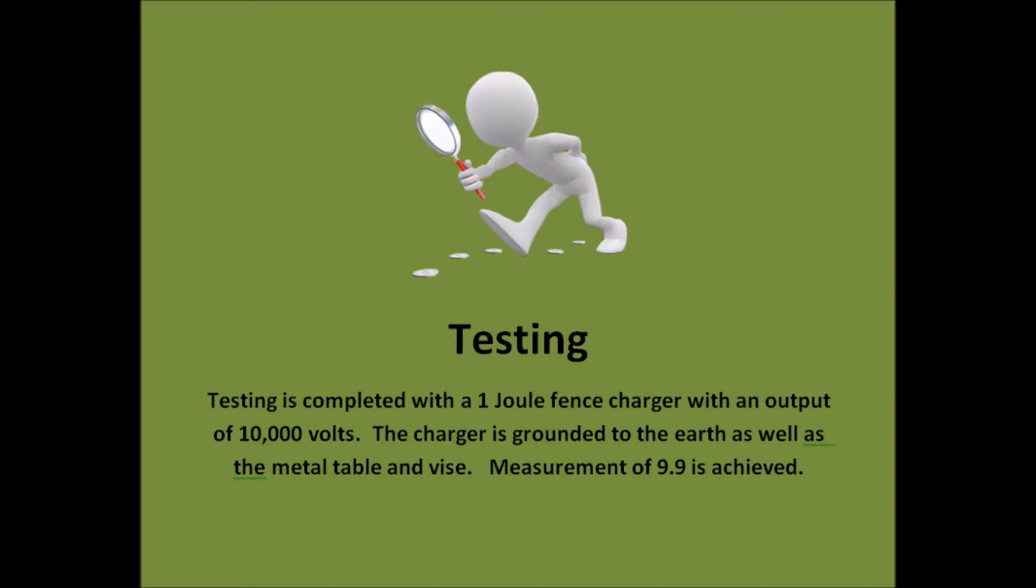Testing is completed with a 1 joule fence charger with an output of 10,000 volts. The charger is grounded to the earth as well as the metal table and vise. We measure each leg so that a measurement of 9.9 is achieved.